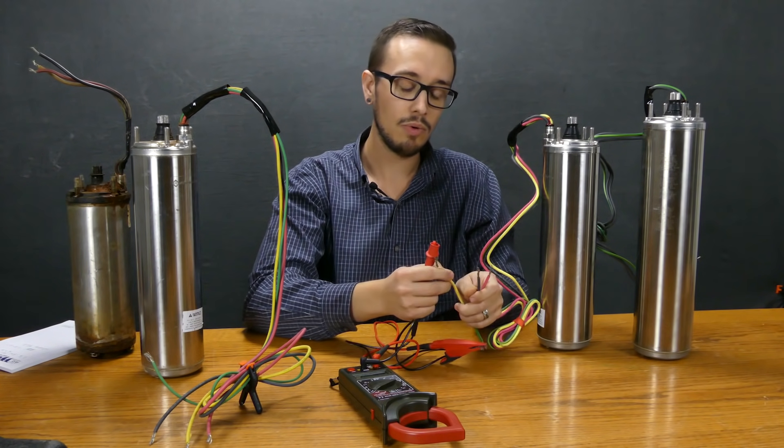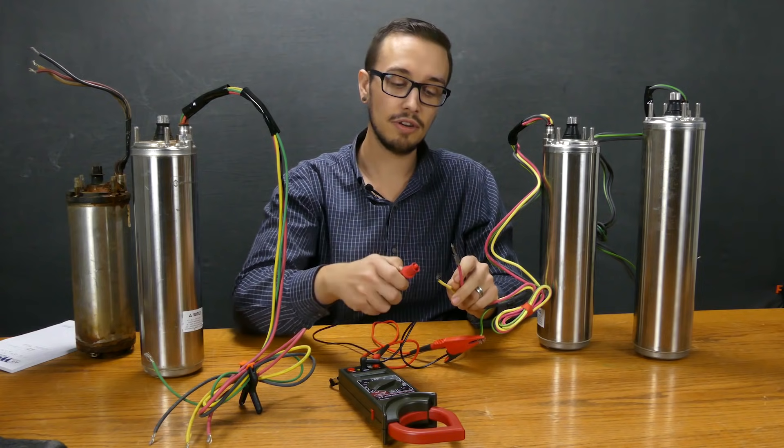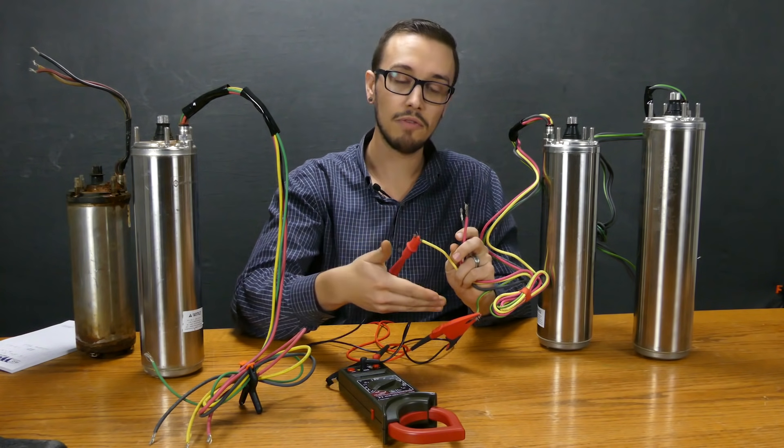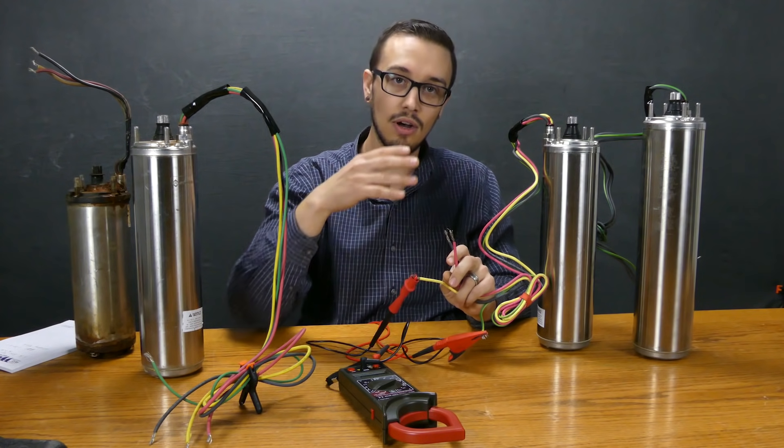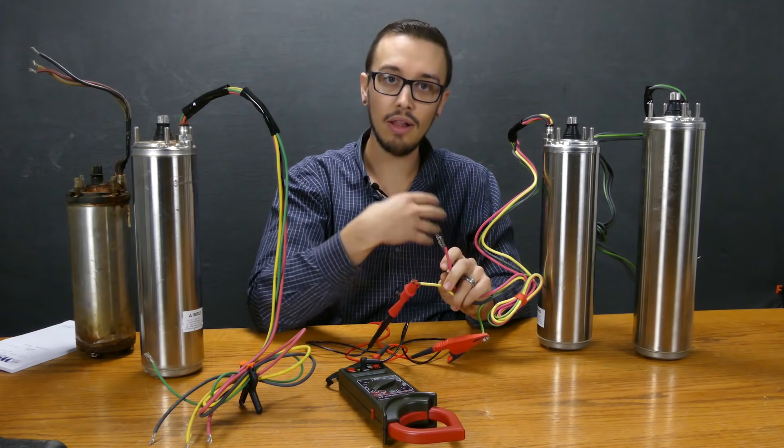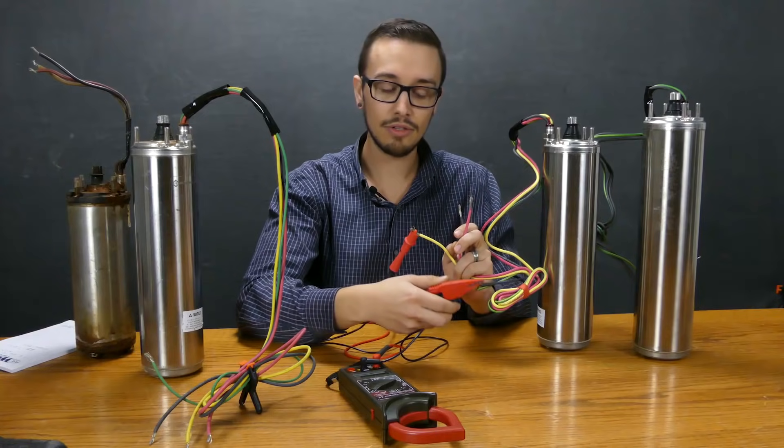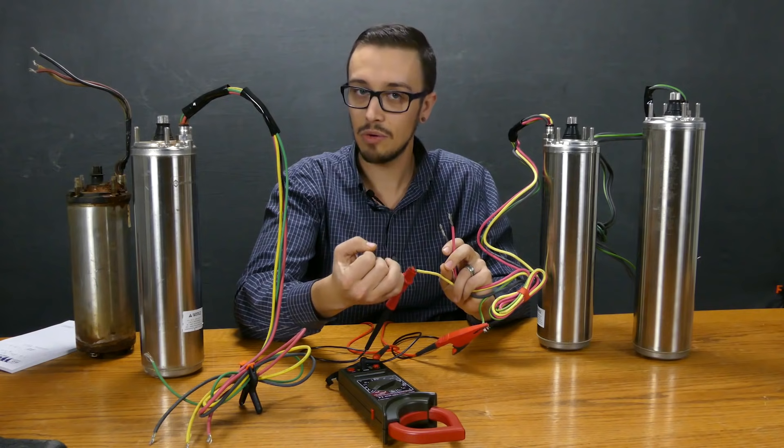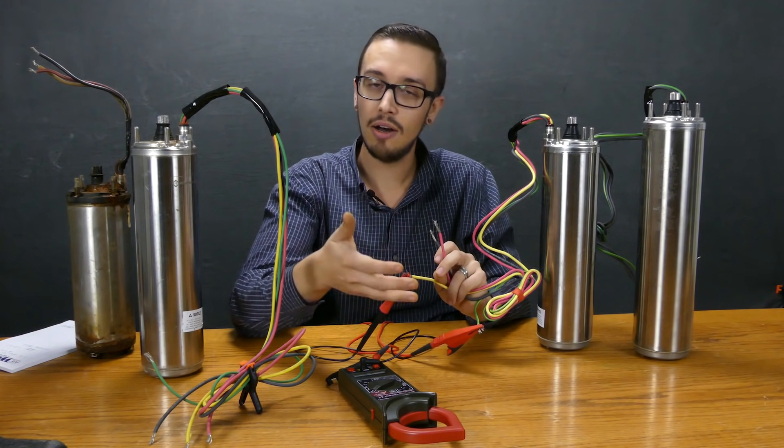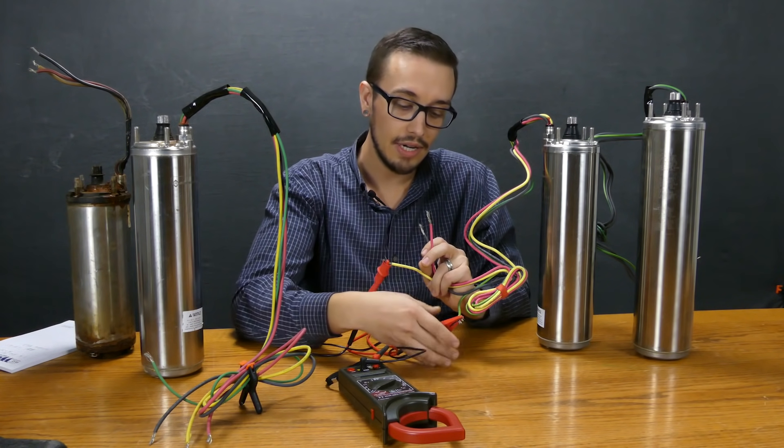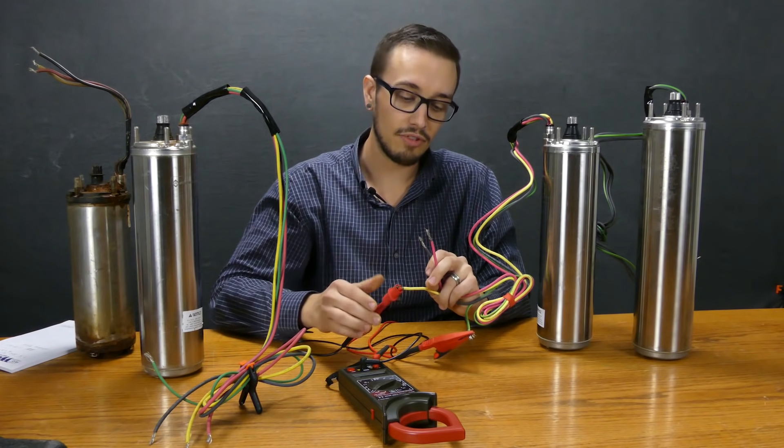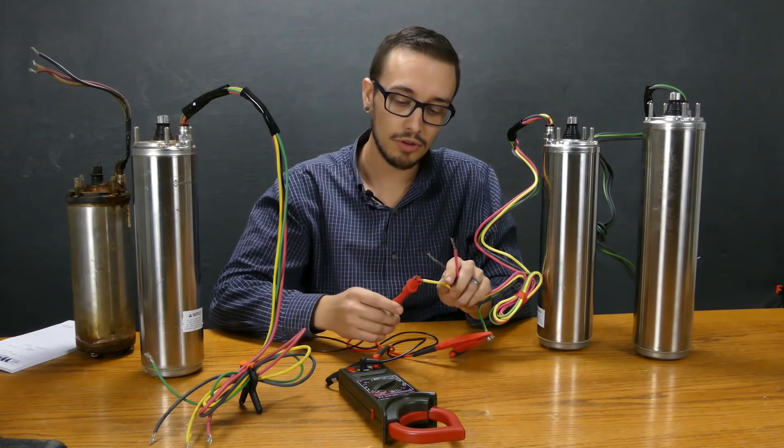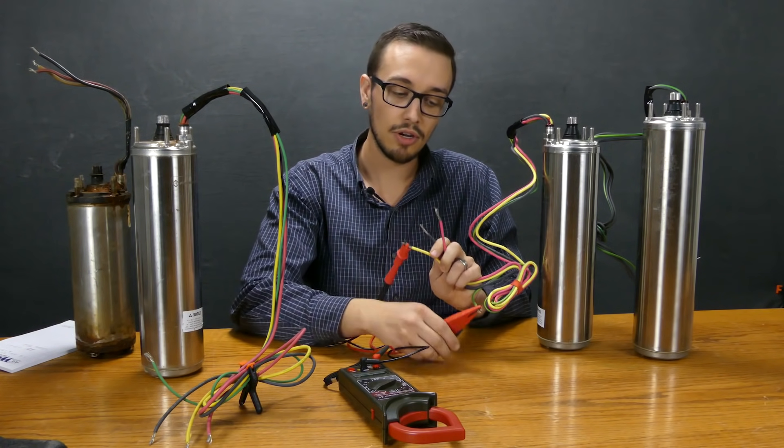So basically all we've got to do with this test is roll through these different leads. We've got one hooked to the ground. Now if you were testing this at the well itself with the pump still down in the well, you can hook your ground to either a ground if you've got one exposed like at a splice, or just hook it right to the well casing if you've got a metal well casing.